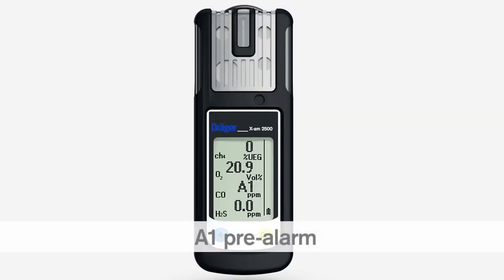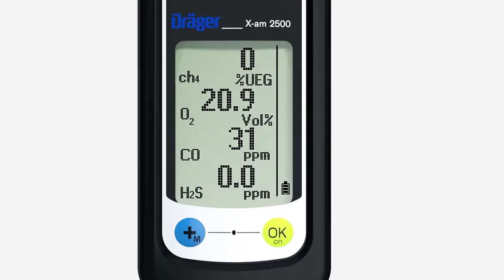The alarm threshold can be changed by using the CC Vision computer software, available free of charge on the product page of the X-am 2500 on the Dräger homepage. The A1 alarm sounds if the concentration is higher than normal but doesn't yet constitute an acute hazard. The audible, visual and vibration alarms are all activated periodically. A1 alternates in the display with the gas concentration. An A1 alarm can be acknowledged by pressing the OK key.